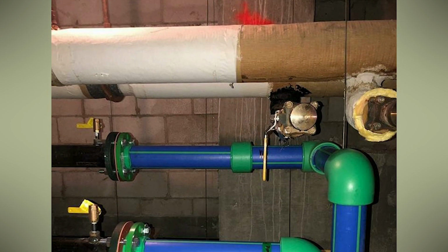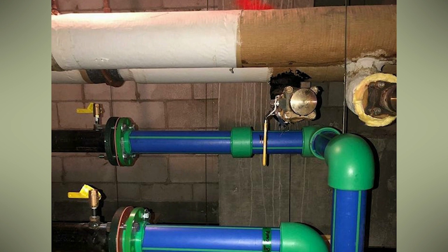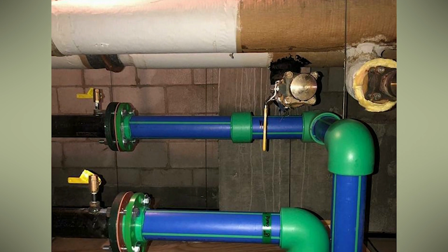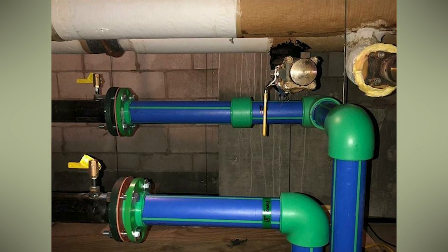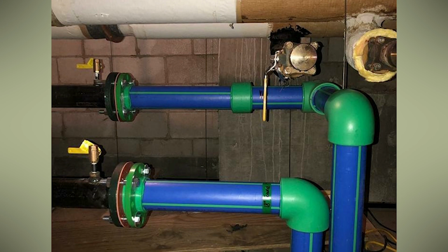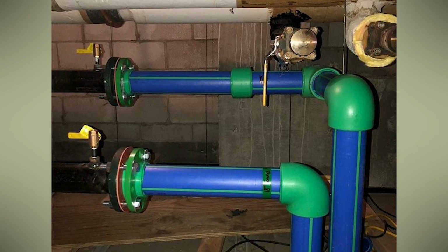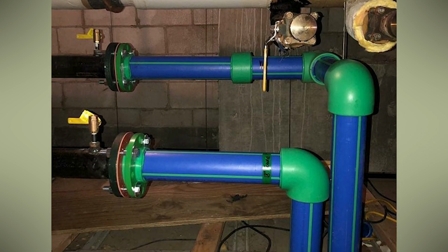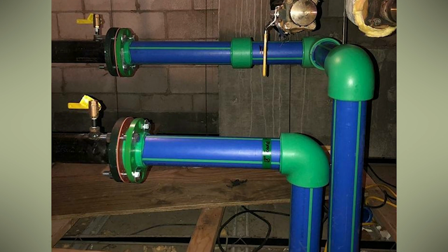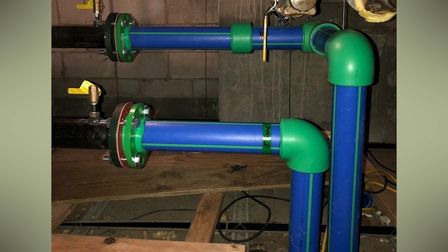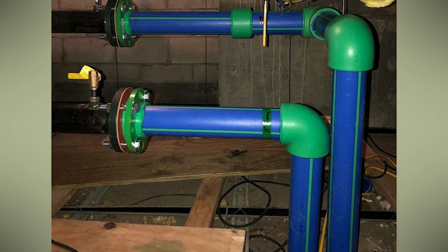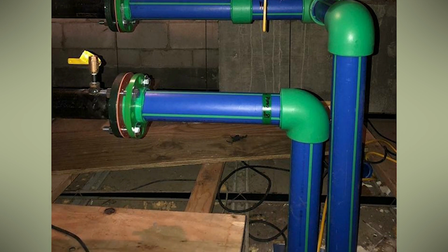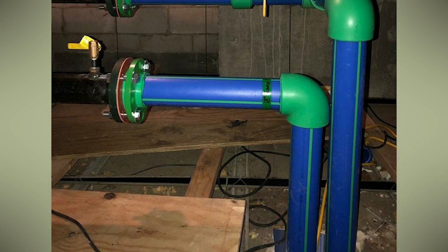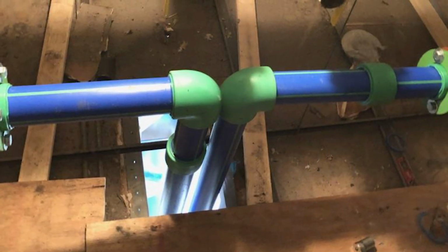More than 6,000 feet of Aquatherm blue pipe SDR11 was installed, ranging in size from half an inch to 4 inches, along with new Raypak boilers, Evapco cooling towers, Bell & Gossett pumps, and JCI-branded water furnace water source heat pumps. Installation was challenging because the floors were concrete slabs 8 inches thick, with 10-inch square blockouts in identical locations from the 4th through 20th floors. The existing risers went straight up through the blockouts without any offsets.